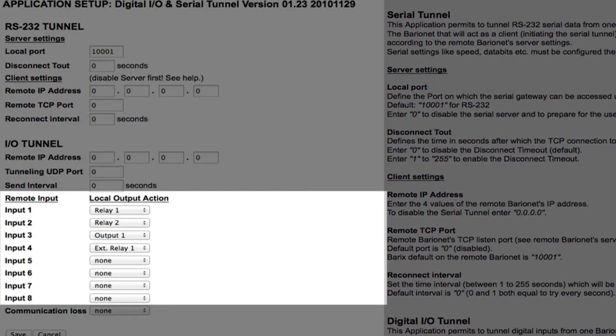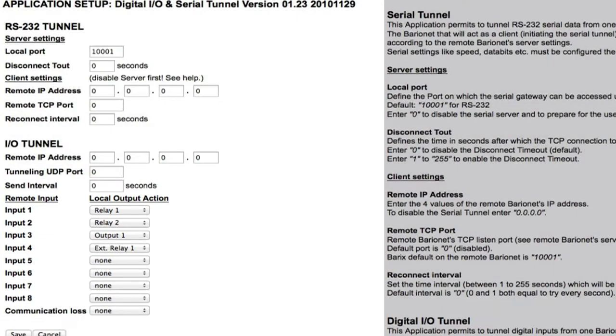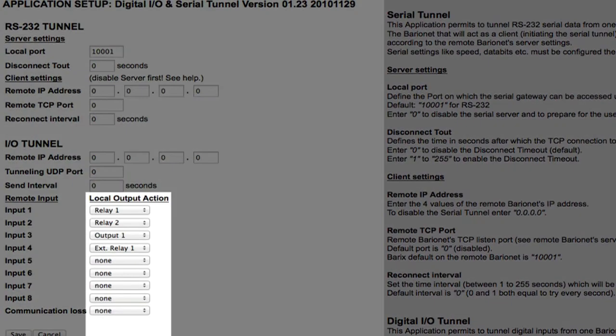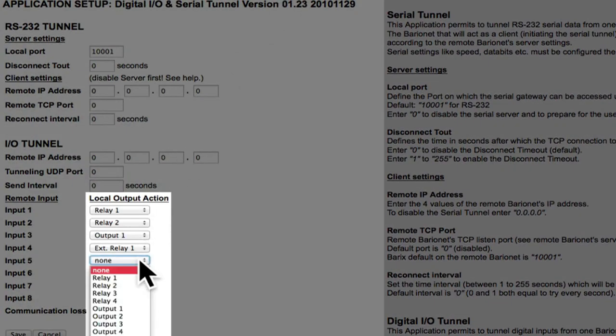The application can be configured so that when an input on one Barionet goes active, an output or relay on the other Barionet goes active as well. The association between inputs on one Barionet and outputs on the opposite Barionet is completely configurable via the application setup screen. Local output action can be directed to specific relays or outputs.